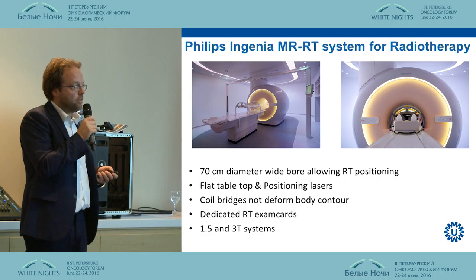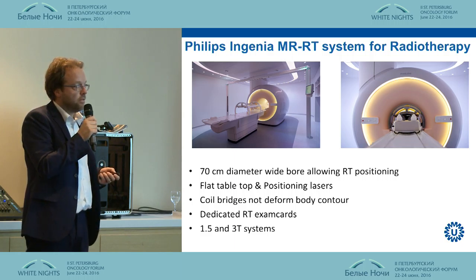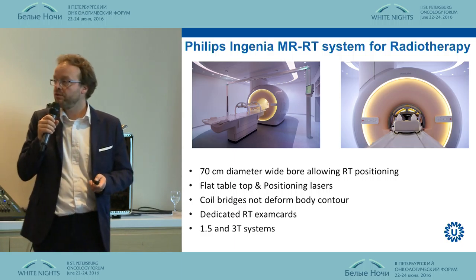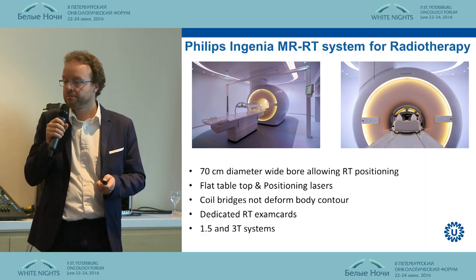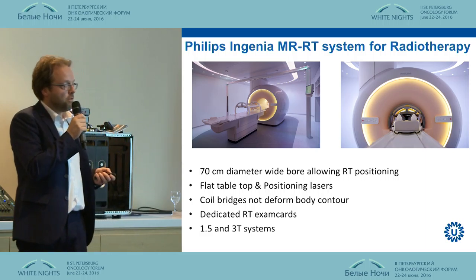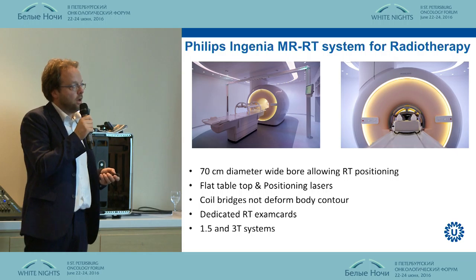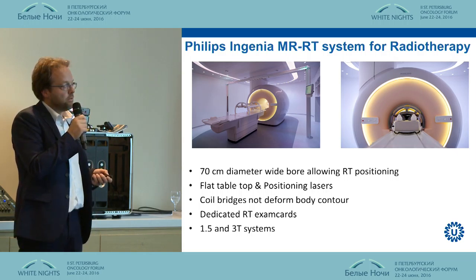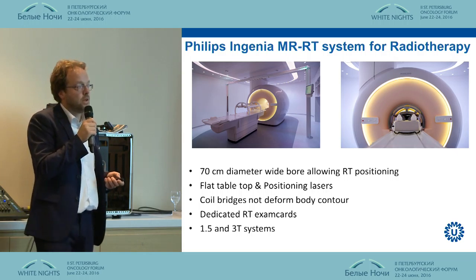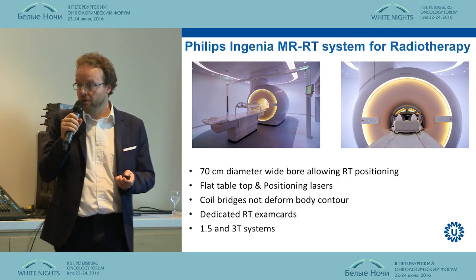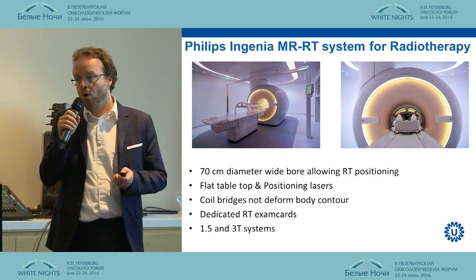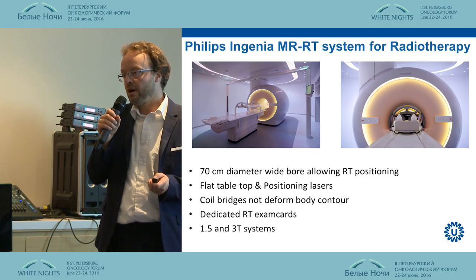It's important that this wide bore is available now, this 70 centimeters, because it allows scanning in RT position. It comes with a flat tabletop and positioning lasers, and dedicated exam cards. We use 1.5 and 3T systems, and all our sites receive our MR scanning.